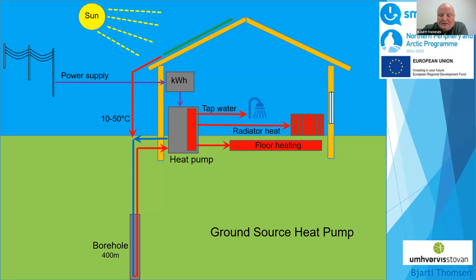One interesting aspect of the heat pump is its efficiency. With a coefficient of performance, the COP, of 4, we use only 1 kilowatt of electric power to extract 3 kilowatts from the ground and produce 4 kilowatts of heating for the house. So it's a very efficient system, and it also has a water tank as storage inside.